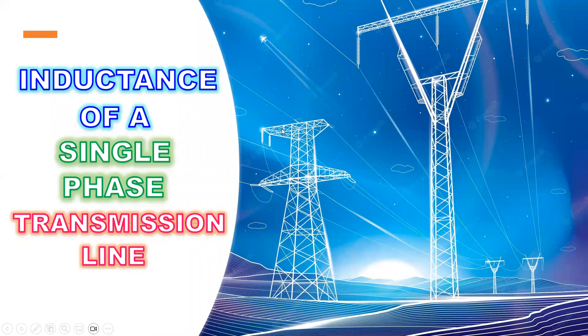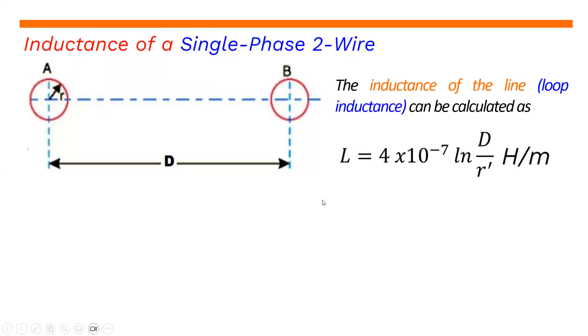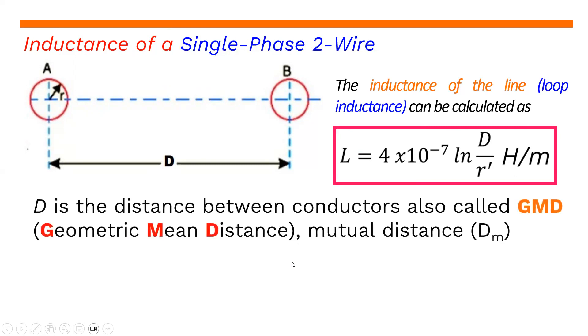So right now I'm going to discuss the inductance of a single-phase transmission line. The inductance of a single-phase 2-wire line, or the loop inductance, can be calculated as L is equal to 4 times 10 to the negative 7 natural logarithm of D over R prime, where the unit will be Henry per meter. Where D is the distance between conductors, also called the GMD, or geometric mean distance, or sometimes also known as mutual distance, or D sub M.